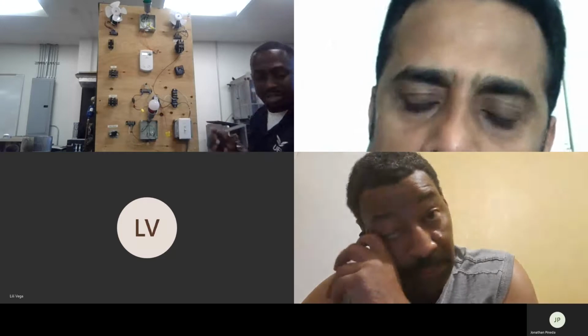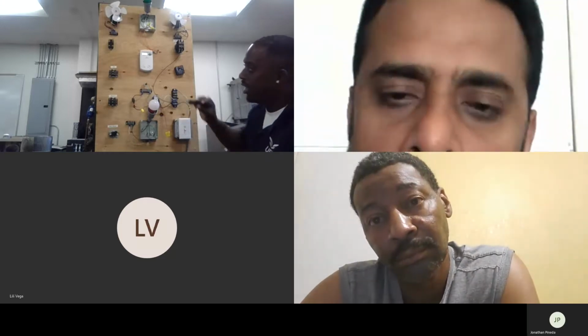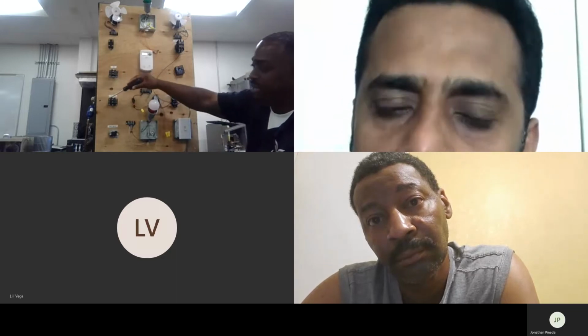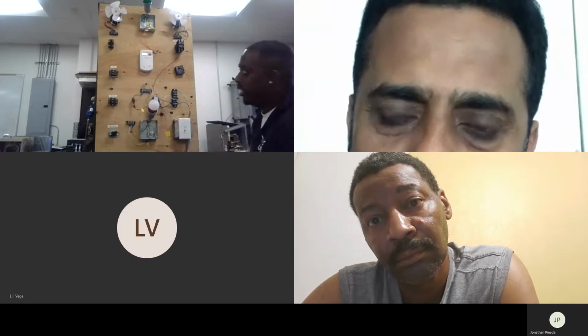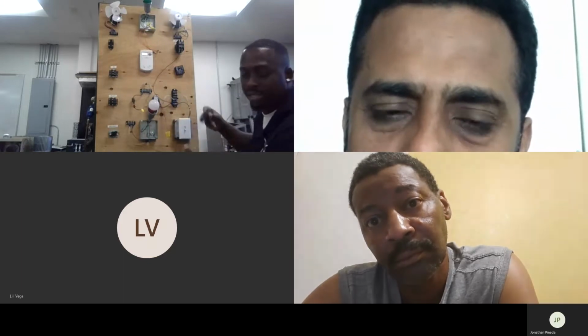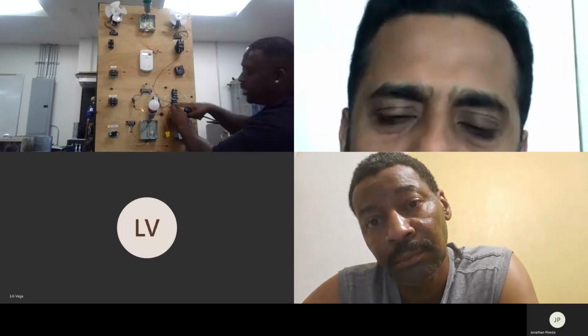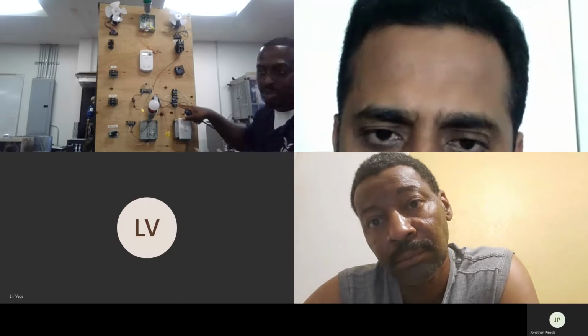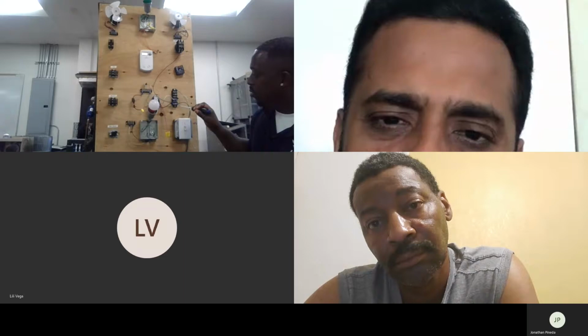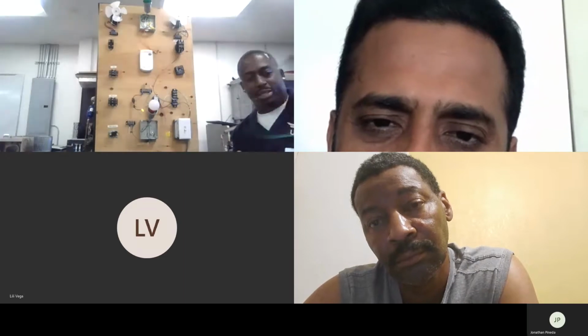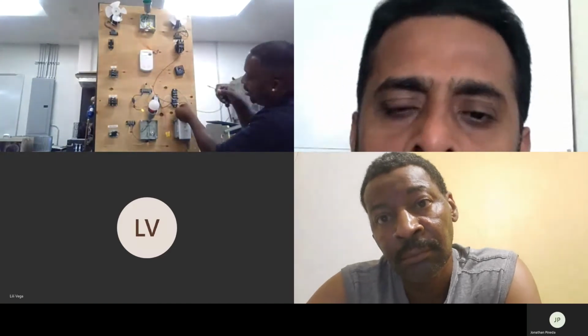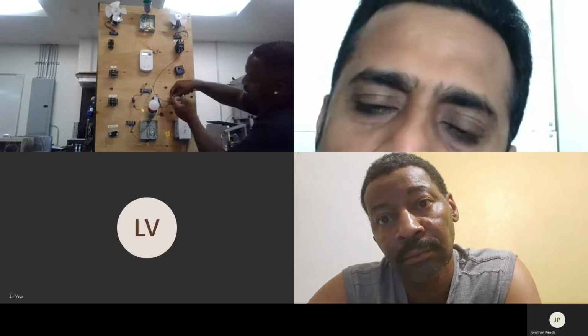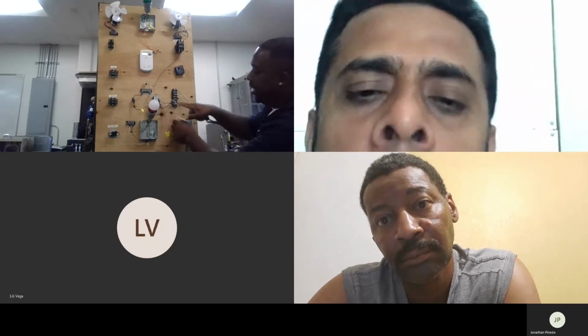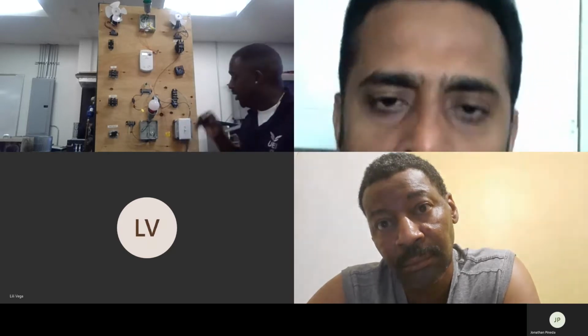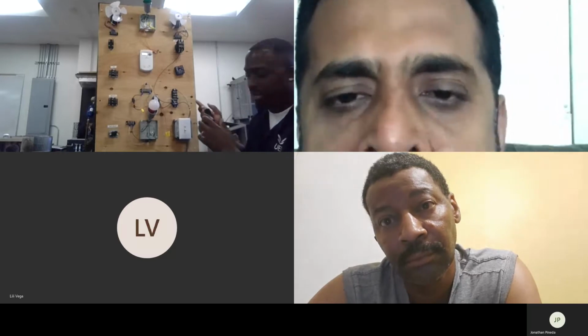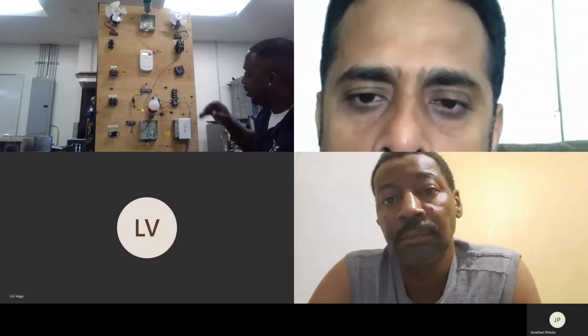Let's say — remember last week we had L1 connected to this relay, and L1 connected to this relay, plus L1 connecting to our transformer. Let's say we had a bigger project with 10 different relays that all needed their own L1. We can only put so many wires on the same terminal before we run out of space. So what you could do, and sometimes in class what we do, is take a small piece of wire, connect it here, and loop it over to here. Now this terminal is also L1, and I could connect another thing there. You can do that however many times you need, because it's just a bunch of little strips of metal conductors, and they'll be energized if you energize them. That's what we use — it's just a means of getting power from one place to another.